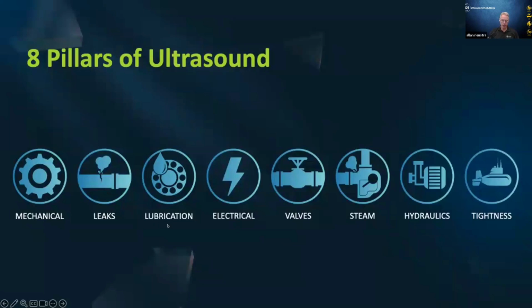Lubrication. Poor lubrication practices are the single biggest cause of bearing failures. In data centers and all kinds of different electrical assets, we have motors running fans for cooling. Those fan bearings need to be lubricated on the right interval. If they're over lubricated, they're going to fail. If they're under lubricated, they're going to fail. What we're doing with ultrasound is listening to and measuring the amount of ultrasound produced by friction in the rolling elements of the bearing. As that friction changes, we know the lubrication film is changing. So we can use ultrasound to guide us on when to lubricate and how much to lubricate.